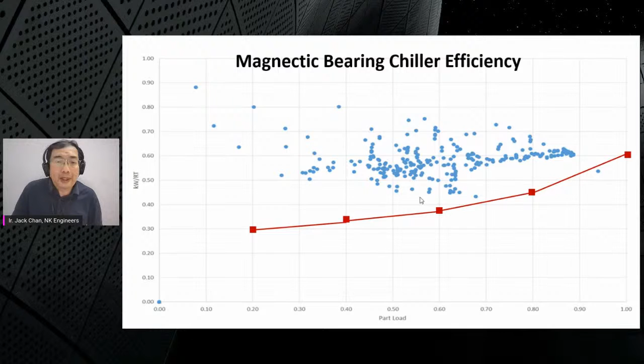But it's very important to compare these two. Once you compare them, we found something. The red ones are the centrifugal chillers, and the blue ones are the magnetic bearing. The magnetic bearing chiller's efficiency is almost constant all the while, but the centrifugal chiller's efficiency actually drops when it goes to very low loads.